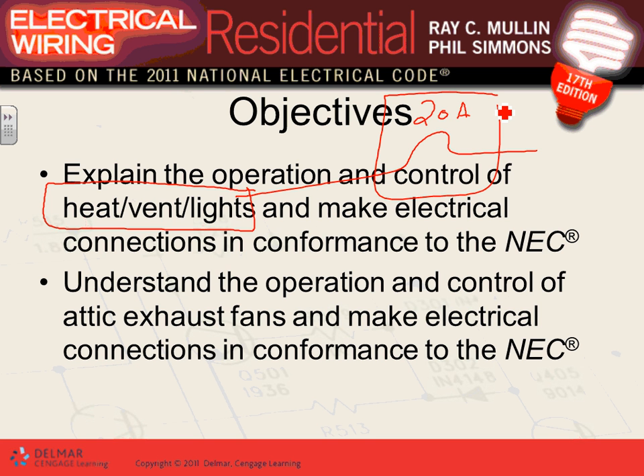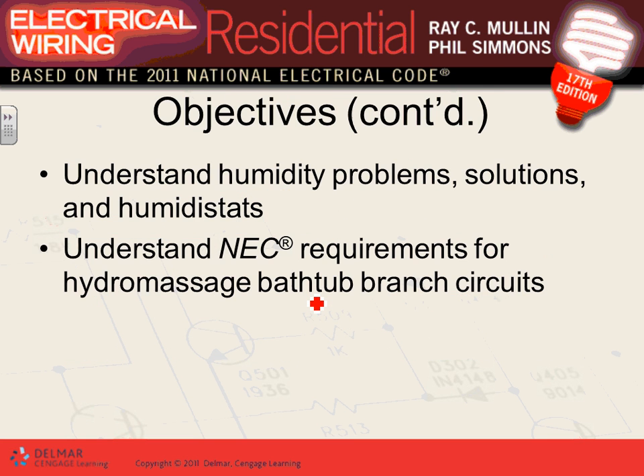We'll talk about the operation and control of these exhaust fans and attic fans and so forth. Humidity problems. When you have a humidistat, guys, we have fans. Where would that be an issue? In the laundry area, you are supposed to provide an exhaust fan for me. How are you going to control this exhaust fan? You can manually turn it on and off, or you can put a humidistat to turn it on and off, or you have a temperature switch to turn it on and off. There are so many ways of controlling that fan, guys.